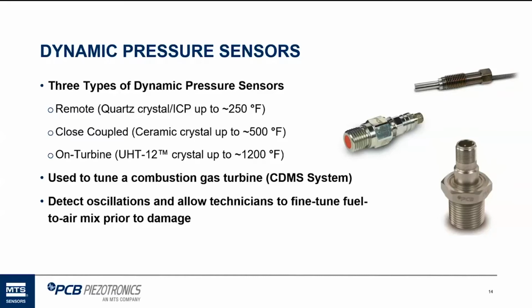There's also a style called a close coupled sensor. It's a ceramic crystal type of sensor, can handle around 500 degrees Fahrenheit, and it's not mounted actually on the turbine, but a little ways away from it, depending on the application and the turbine. There's a tube that goes straight to the sensor, and it's mounted away from the heat for monitoring combustion dynamics. That method and the other method were what they used to do many years ago for looking at combustion dynamics on gas turbines.